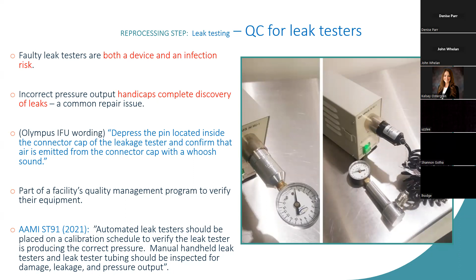The IFU for this says turn it on, and the part where it connects to the scope, there's a pin inside there. You depress it and you listen for a whoosh sound. But from one person to the next, what does that mean? There's no way to know how much PSI that represents. For many years, everyone expected, well, this is a piece of equipment, so biomed must check that. Well, all they've been able to do up till now is electrical safety testing. But now there are options for measuring, as you see in the picture, by attaching gauges. It's a very quick test, but it's a test that's recommended per AAMI and AORN to be done every day that a leak tester is used.